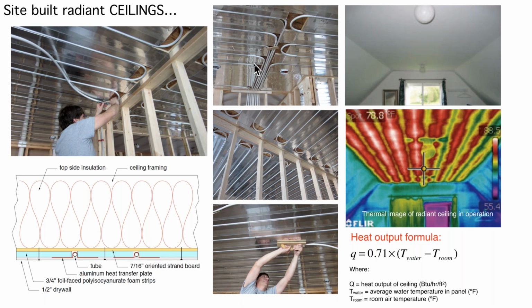And the manifold is actually down in the basement. The manifold does not have to be above the circuits. It's possible to purge the air out of that quite easily, actually, with the manifold being lower than the circuits. And of course, the final step is going to be install drywall over all this.